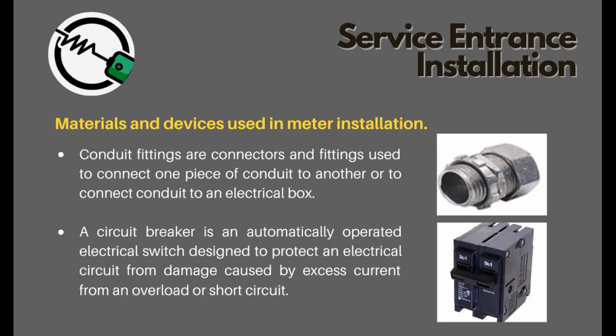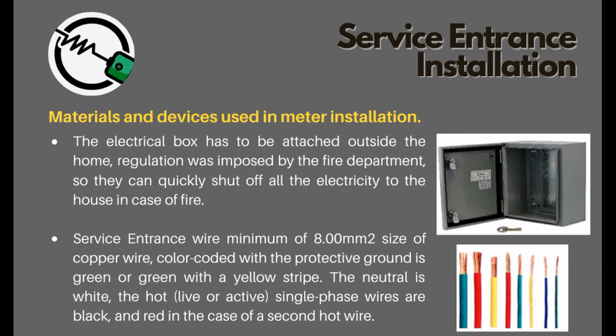Conduit fittings are connectors and fittings used to connect one piece of conduit to another or to connect conduit to an electrical box. A circuit breaker is an automatically operated electrical switch designed to protect an electrical circuit from damage caused by excess current from an overload or short circuit. The electrical box has to be attached outside the home. Regulation was imposed by the fire department, so they can quickly shut off all the electricity to the house in case of fire. Service entrance wire: minimum of 8.00 square millimeters size of copper wire, color coded with a protective ground that is green or green with a yellow stripe.